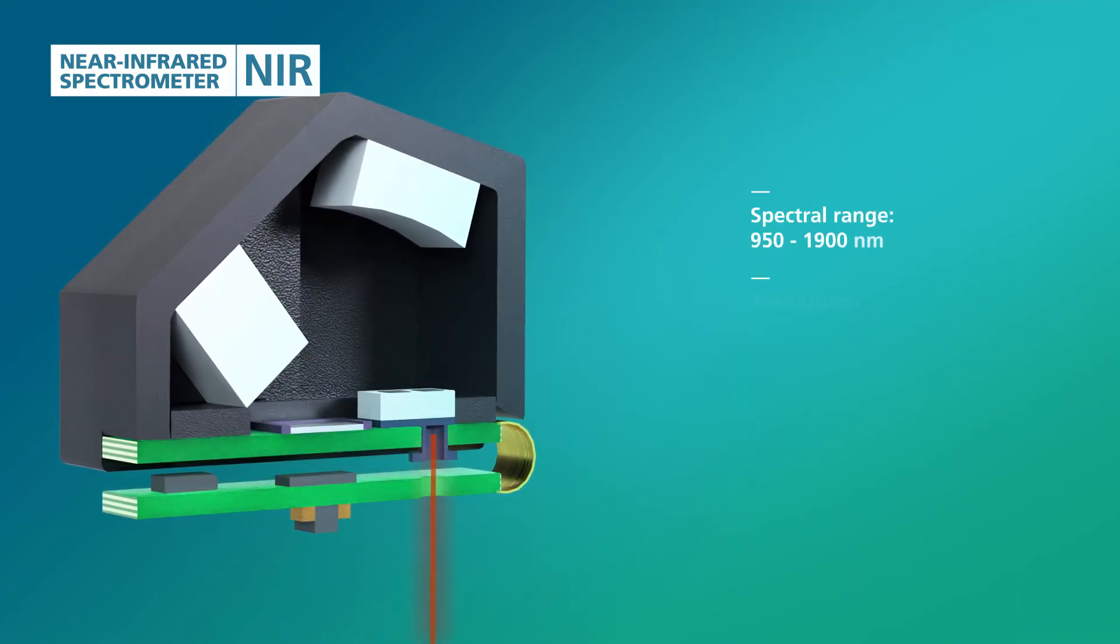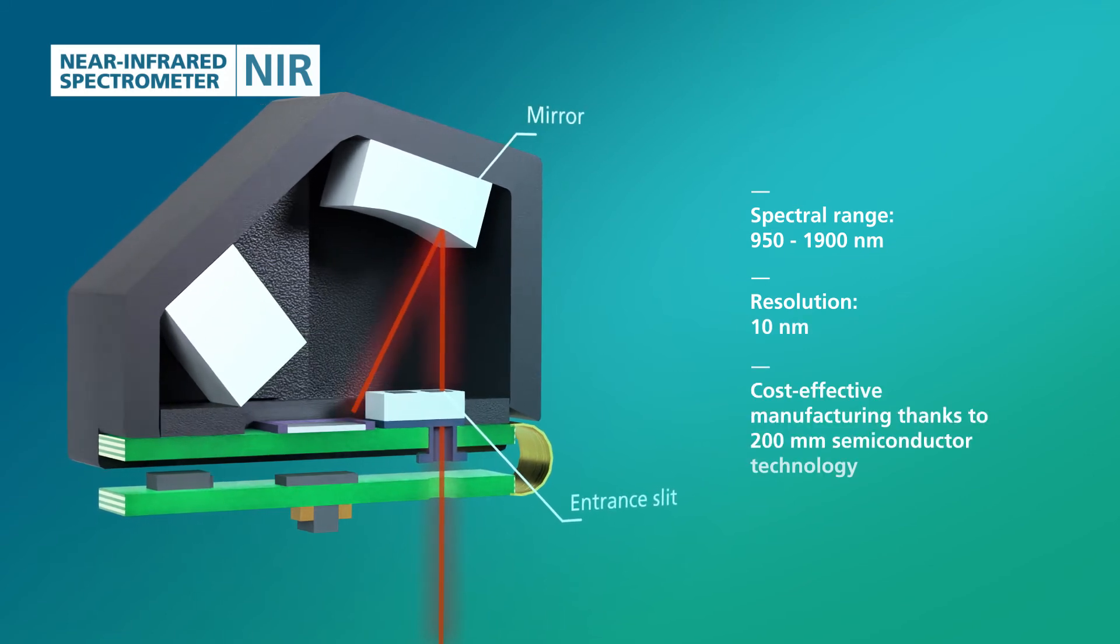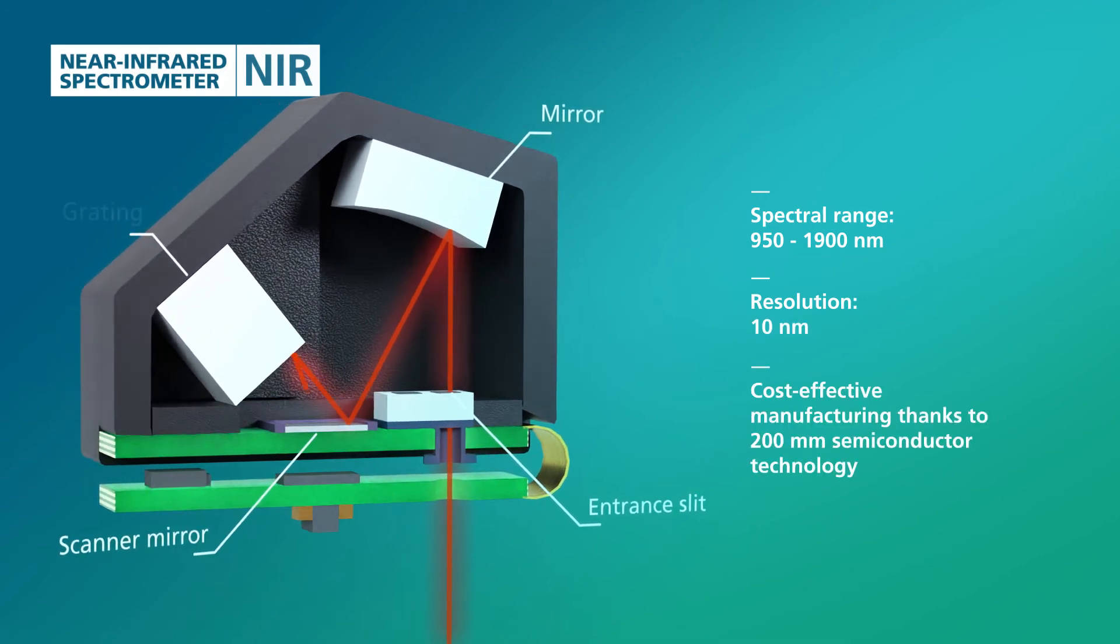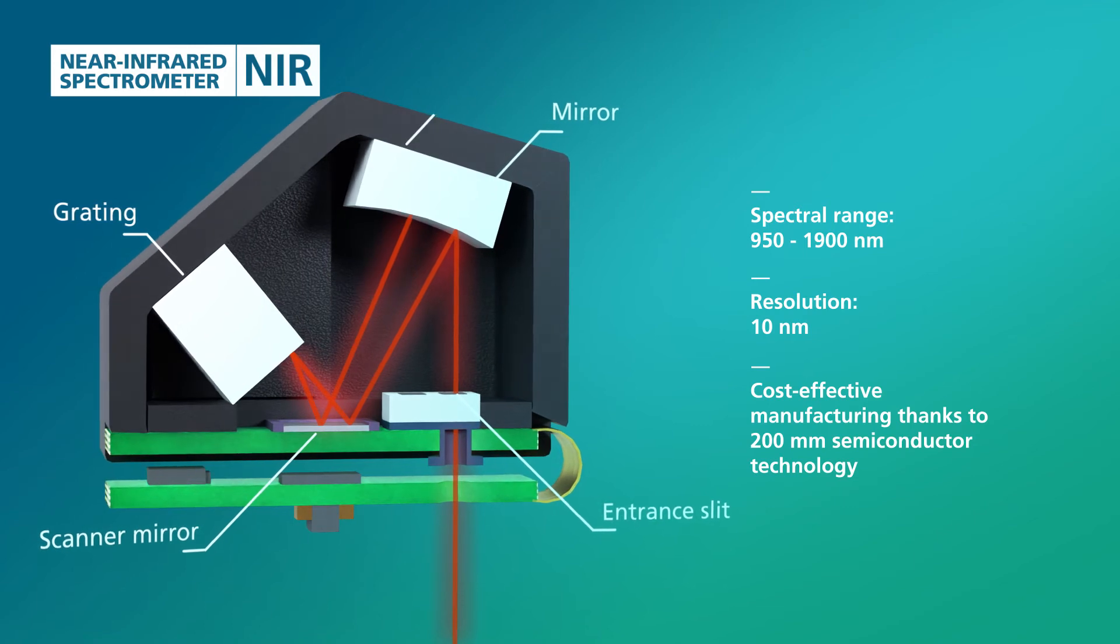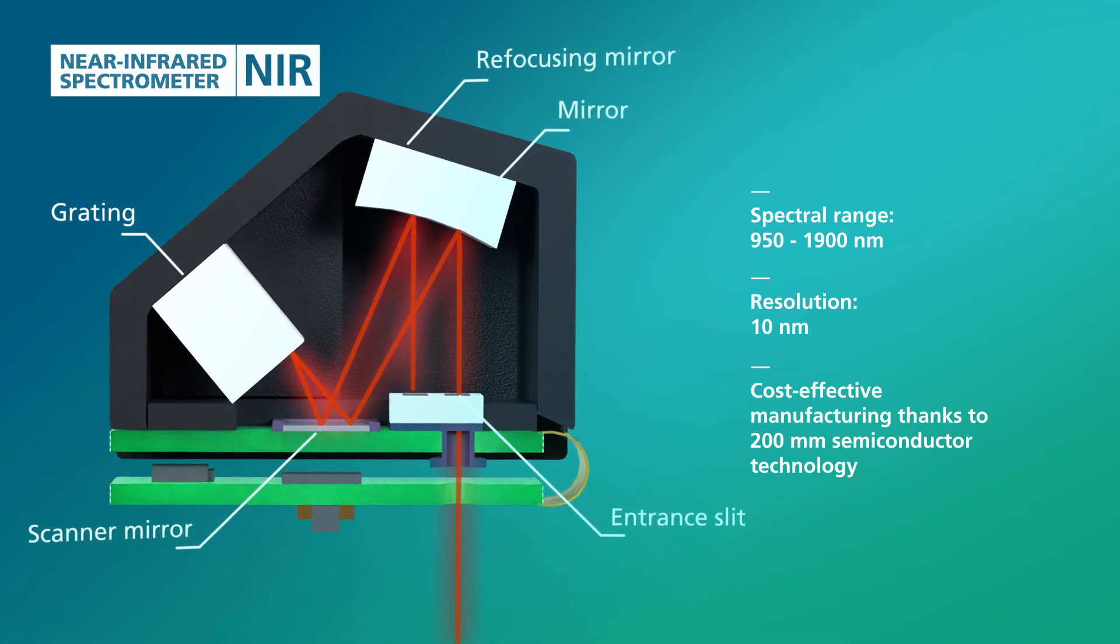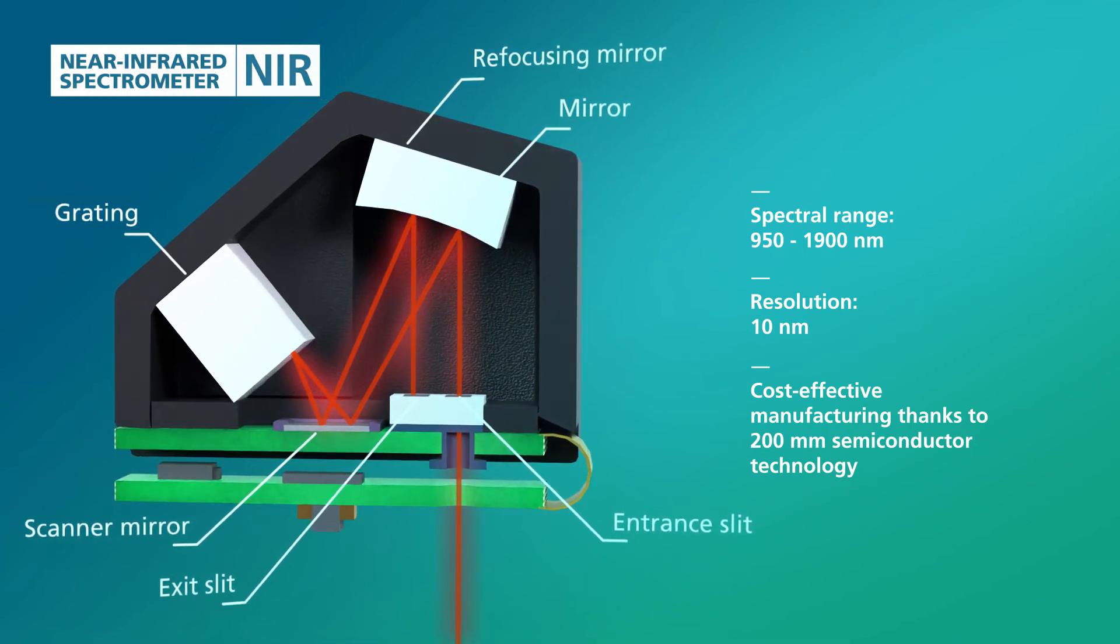The light is spectrally split and falls back onto the mirror and then, via the refocusing optics and the exit slit, onto one or more detectors. The grating can be exchanged easily. This allows modularity in the spectral range and the resolution of the spectrometer.